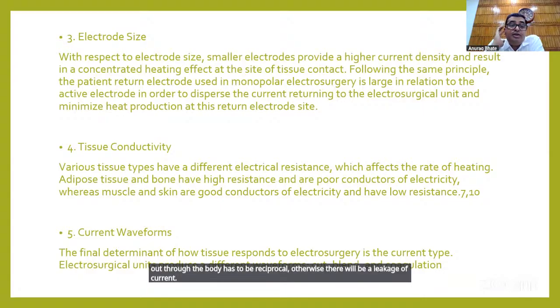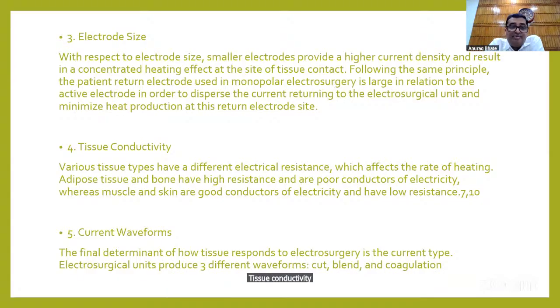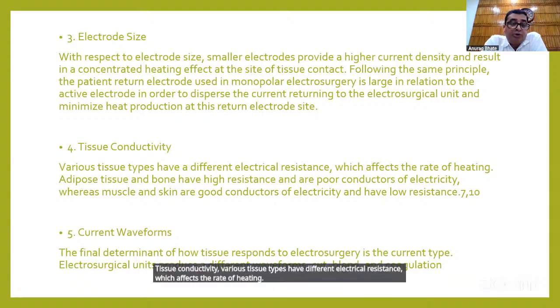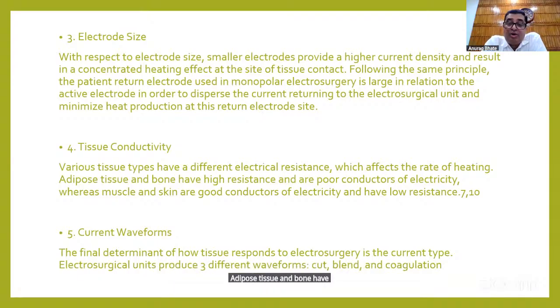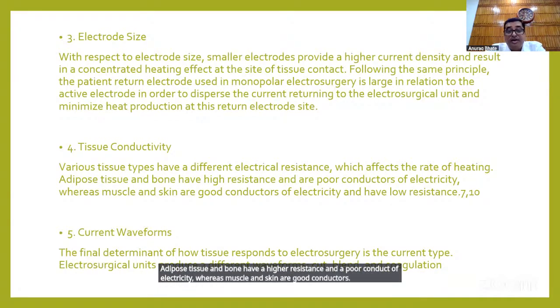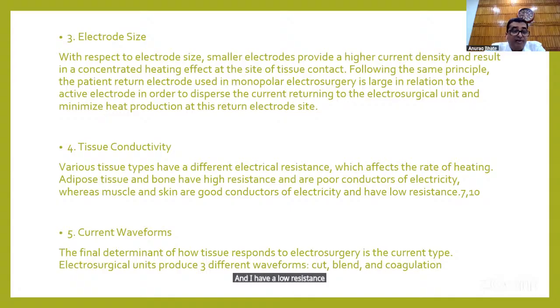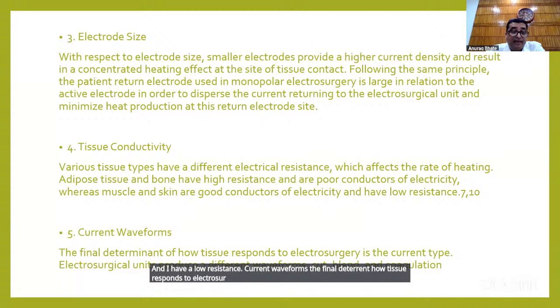Tissue conductivity. Various tissue types have different electrical resistance, which affects the rate of heating. Adipose tissue and bone have a higher resistance and are poor conductors of electricity, whereas muscle and skin are good conductors and have a low resistance. Current waveforms. The final determinant of how tissue responds to electrosurgery is the current type. Electrosurgical units, again, have three different waveforms: cut, blend, and coagulation.